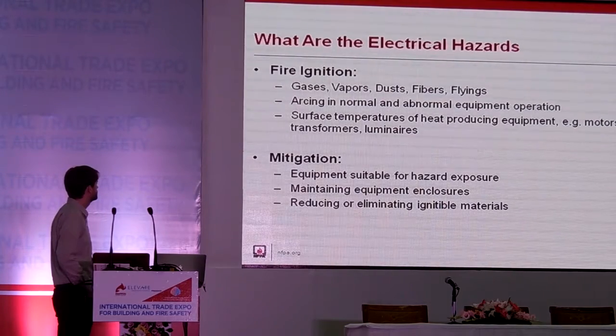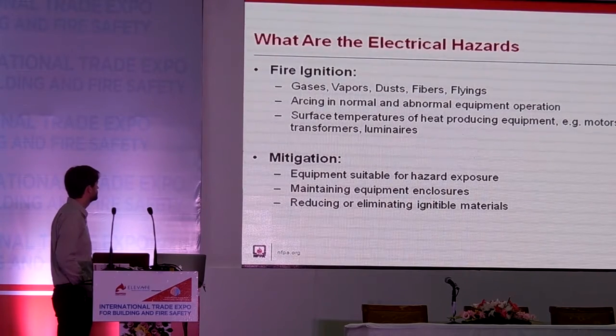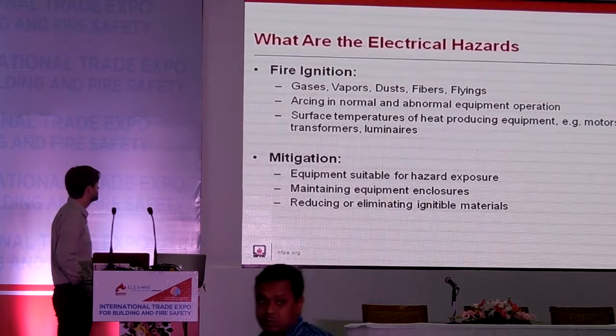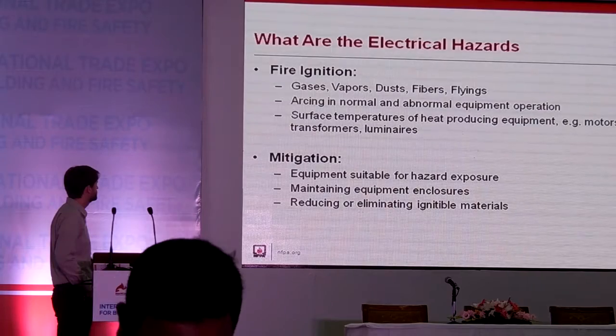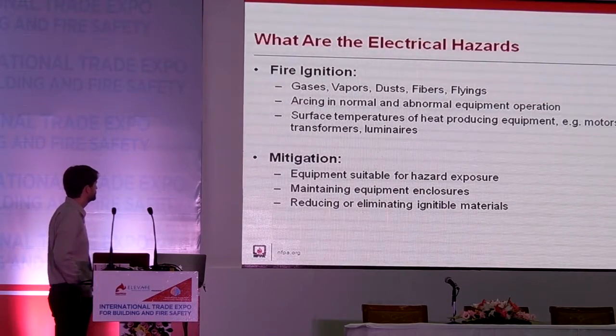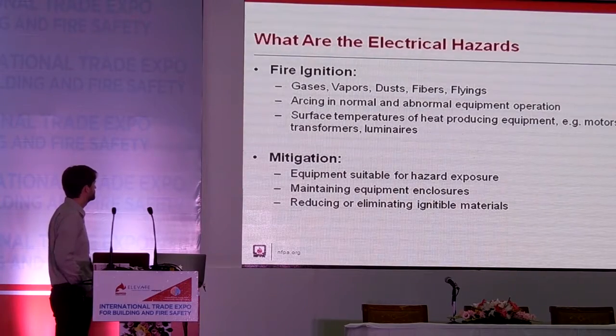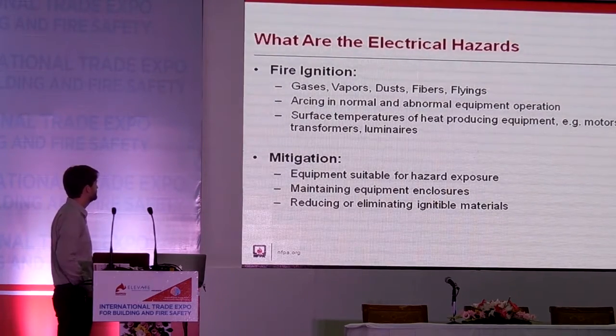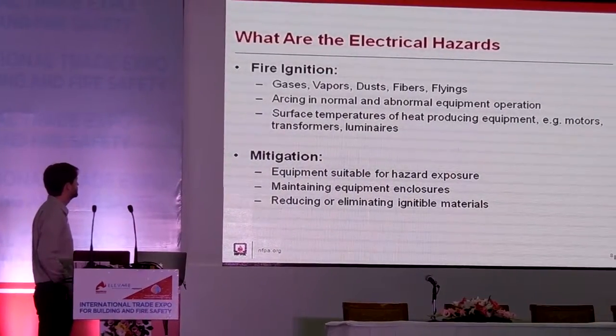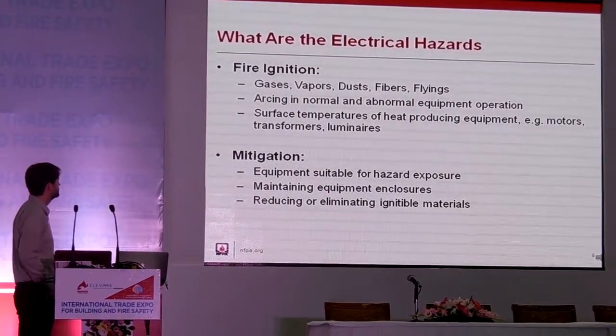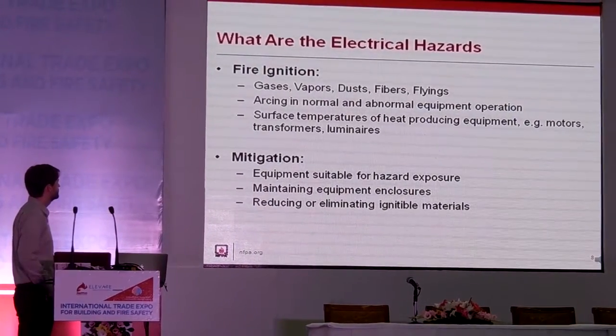Within the garment manufacturing industry, there are a number of processes in which the electrical equipment may provide that ignition source. Where dyes or other solvents are being used, ignitable gases and vapors from flammable liquids can be ignited by normal arcing of electrical equipment. Dusts and fibers and flyings that accumulate on electrical equipment may ignite due to the heating and the entrapment of heat that occurs on the surface of the electrical equipment.